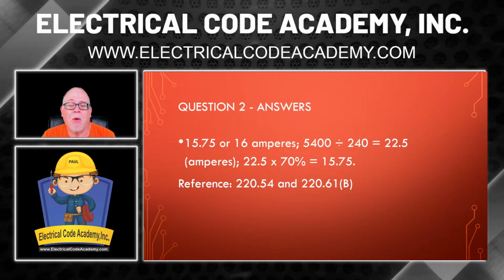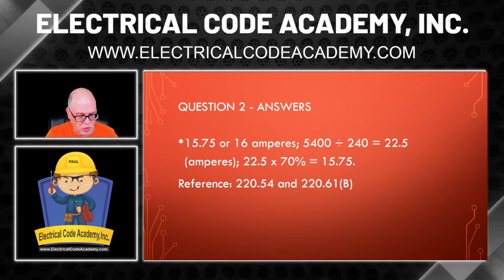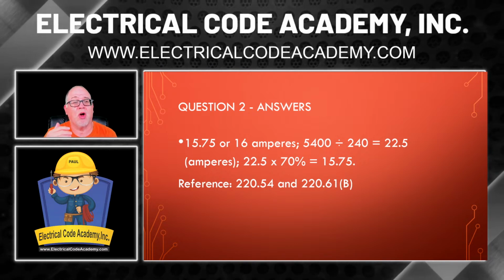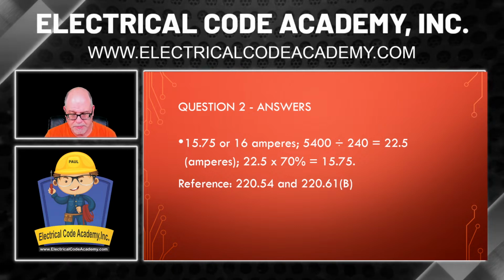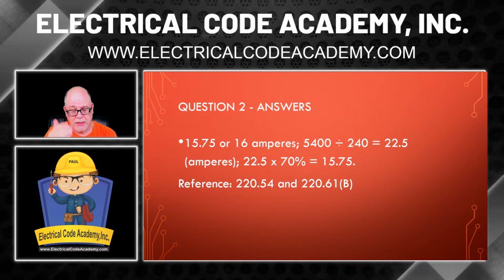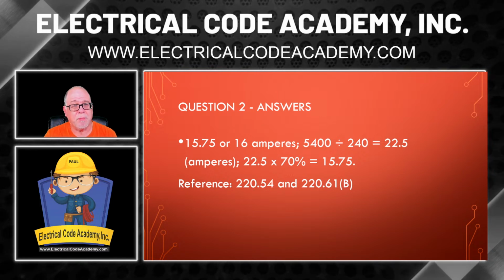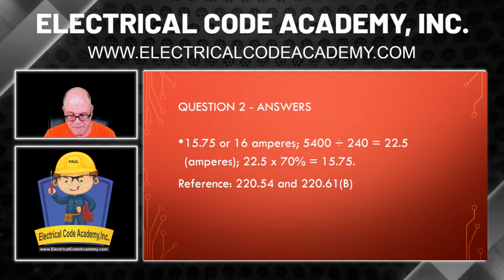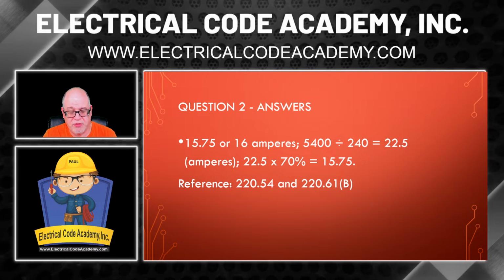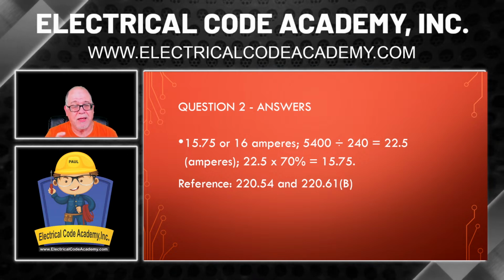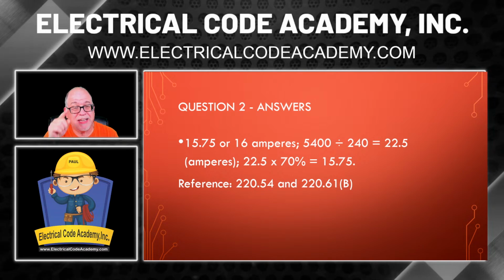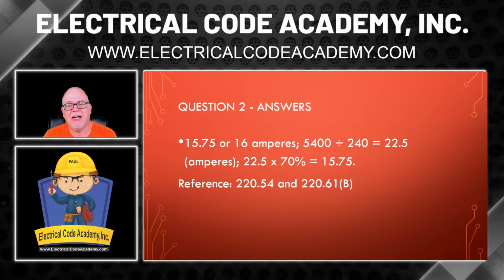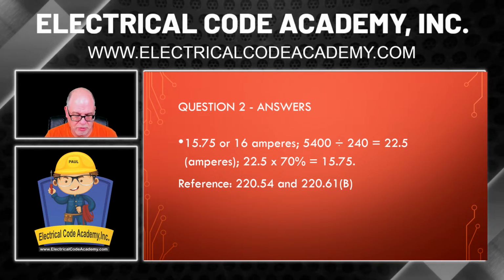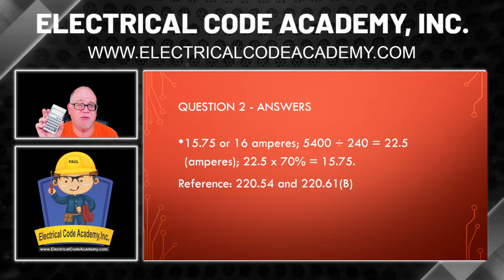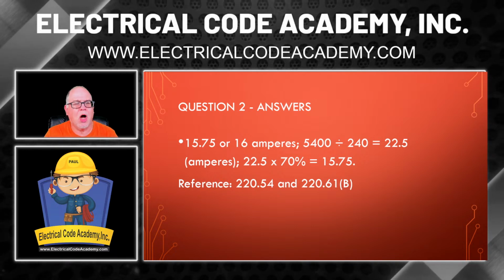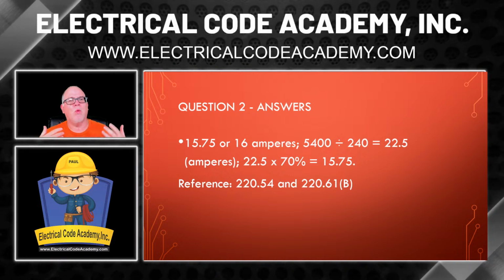Now, I want to talk about the other way you could have done this. So one other way you could have done this is start with our full value, our 5,400, right? 5,400, and you could have multiplied that by 70%. And that gives you 3,780 VA. Then you could take that and divide that by 240 volts. And that also gives you 15.75. Always remember, there are many ways that you can do this.